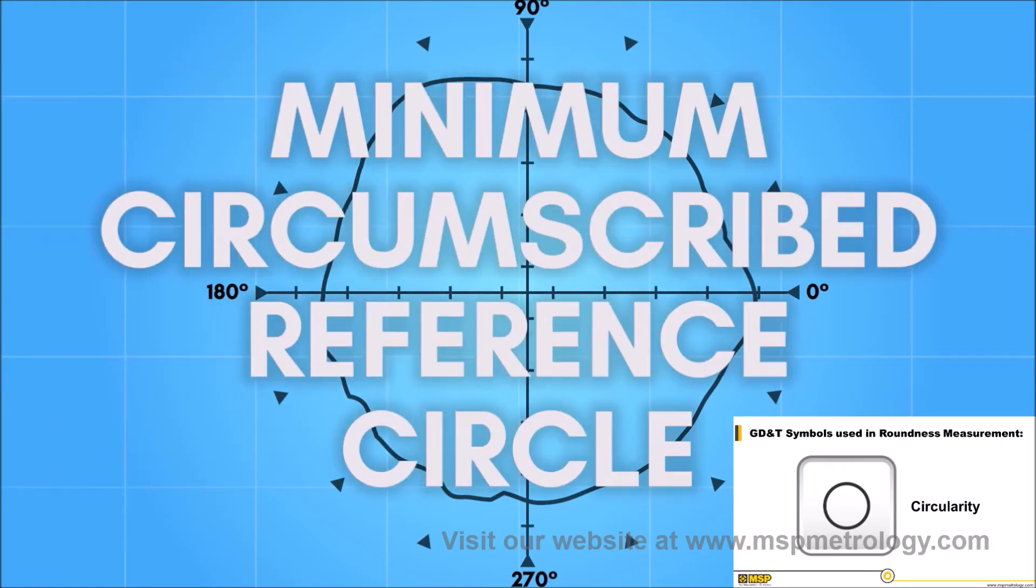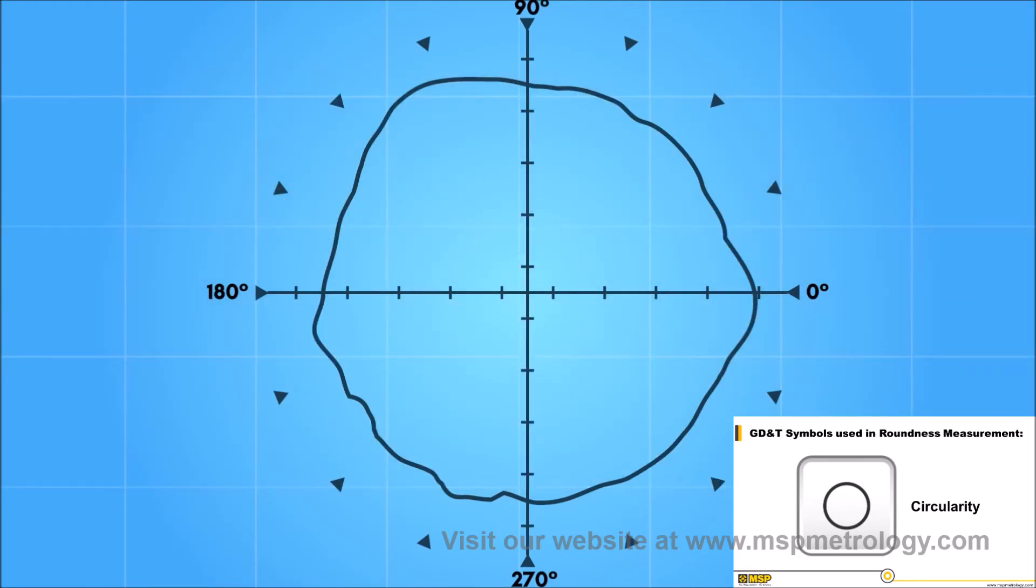A minimum circumscribed reference circle, sometimes known as the ring gauge reference circle, is the smallest circle that totally encloses the data. Out of roundness is quantified as the maximum deviation of the data from this circle.